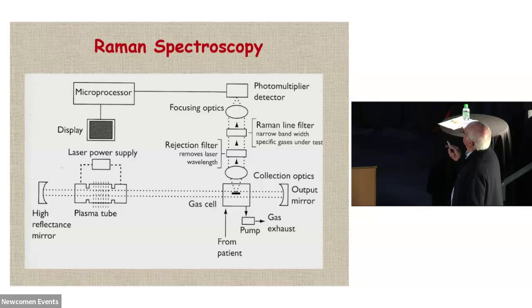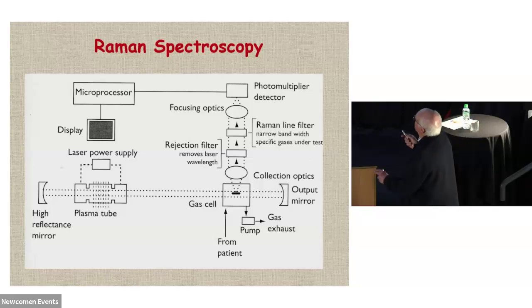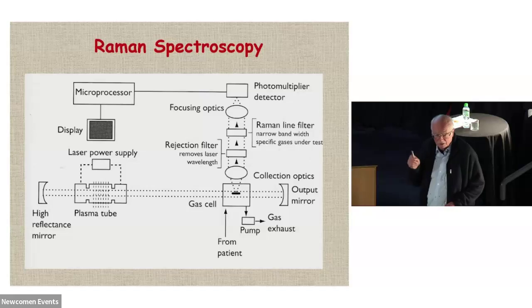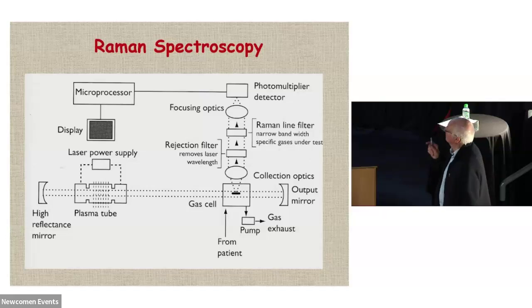But basically, there's a laser here which bashes the gas which is passed through here from the patient. It's sucked through this little chamber, and it's a helium-neon laser that's used. And the thing about Raman spectroscopy is if you bash a molecule with an intense laser, the different gases will emit a secondary radiation at a very small amount, but that amount will be proportional to whatever the agent is you're measuring. So the laser here bashes the molecules there.